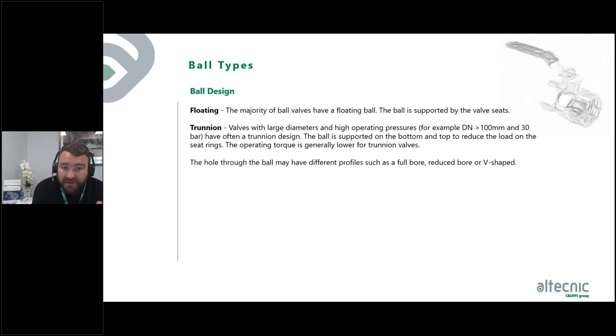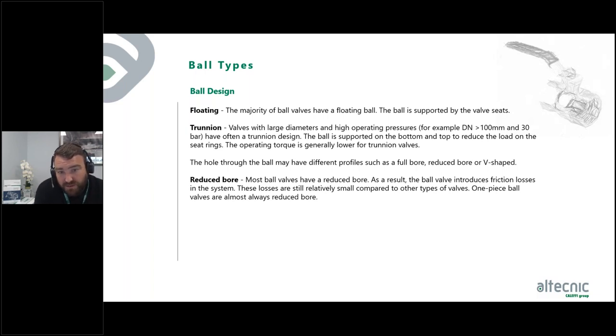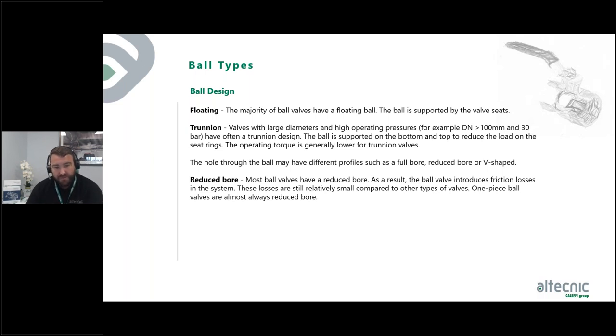The hole through the ball can have different profiles: full bore, reduced bore, or V-shaped. A reduced ball is quite common on entry-level valves — most ball valves have a reduced ball and as a result introduce some friction losses into the system, though these losses are still relatively small compared to other valve types. One-piece ball valves are almost always reduced bore. The bore is smaller than the pipe, which causes a step-down effect and can affect flow.